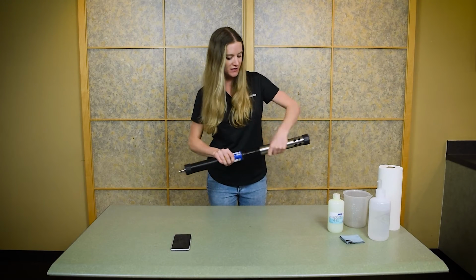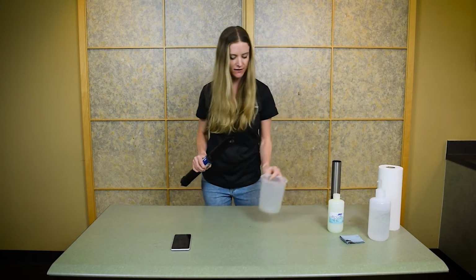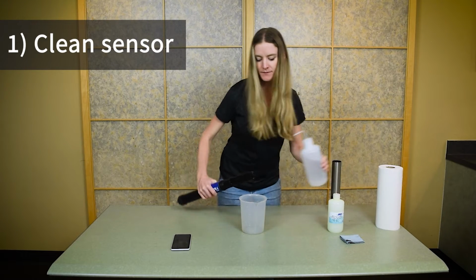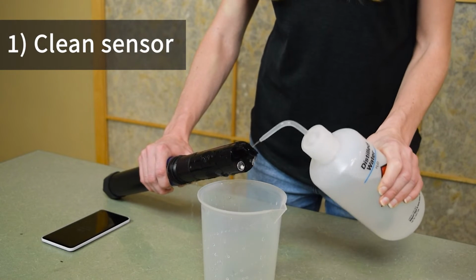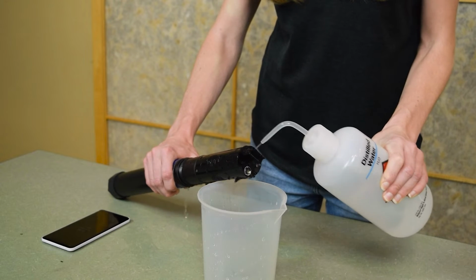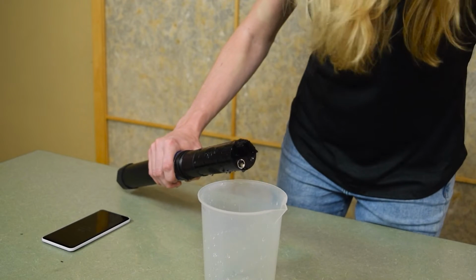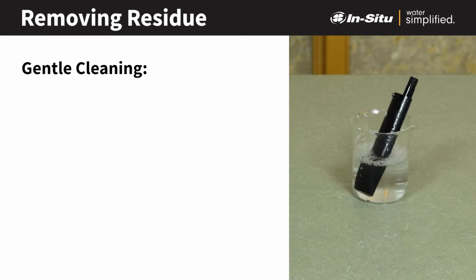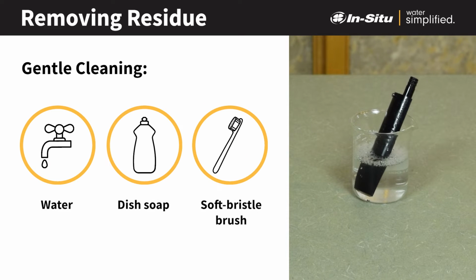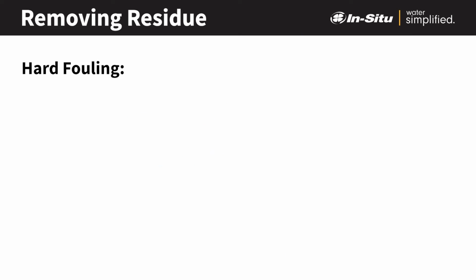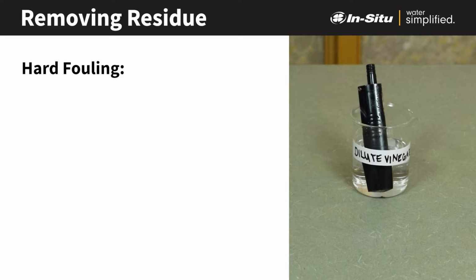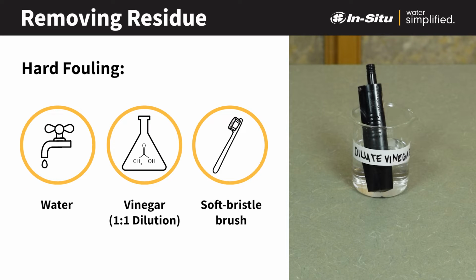First, we'll want to start by cleaning the sensor. Remove the restrictor from the instrument and rinse the sensor with clean water to remove any buildup. If more thorough cleaning is needed, you can remove the sensor and soak it in a solution of dish soap and warm water, and then brush it gently with a soft bristle brush. If there is hard fouling that needs to be removed, soak the sensor in dilute vinegar and then scrub it gently with a soft bristle brush. You can repeat either of these steps as needed.